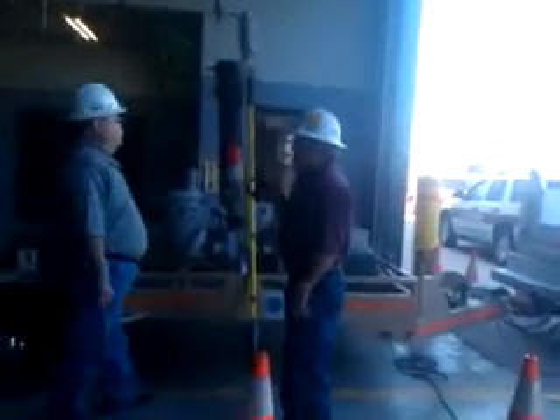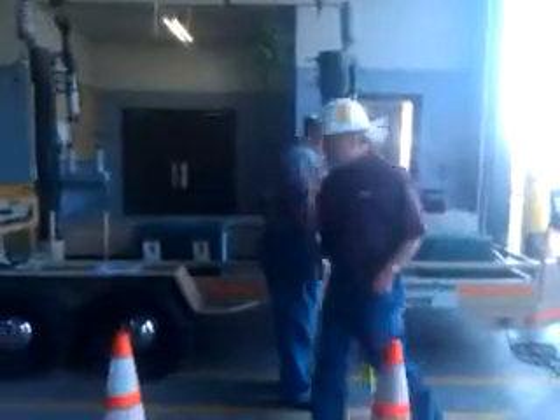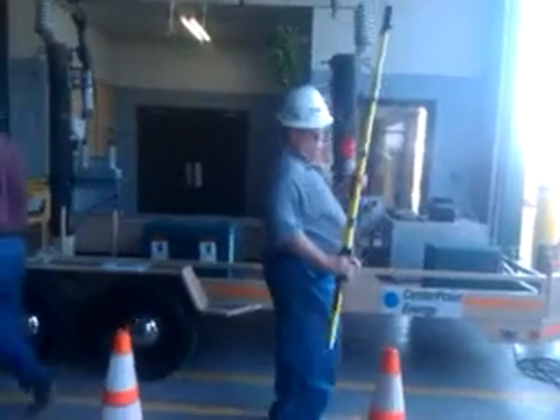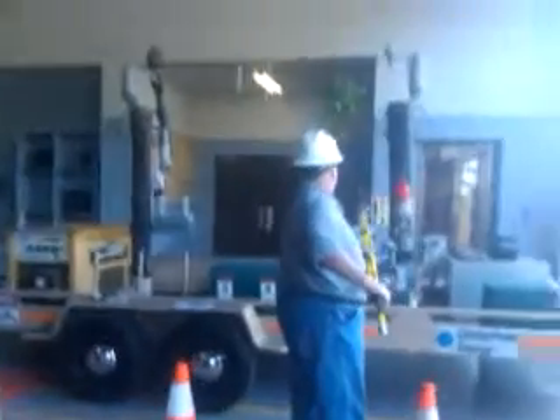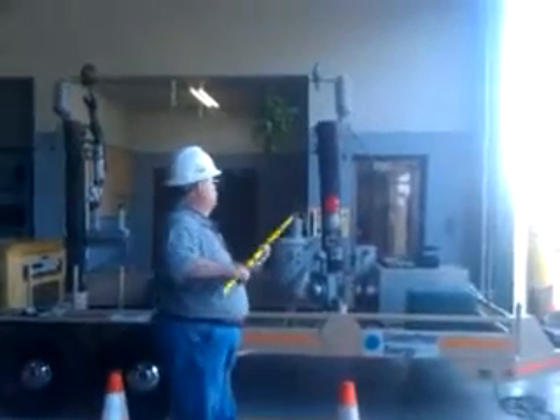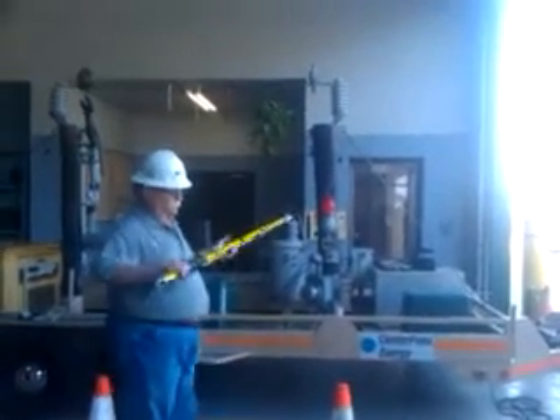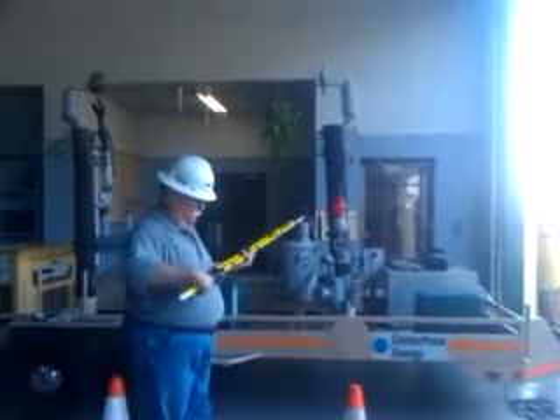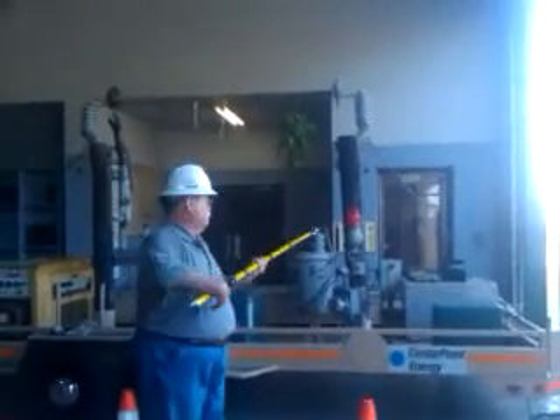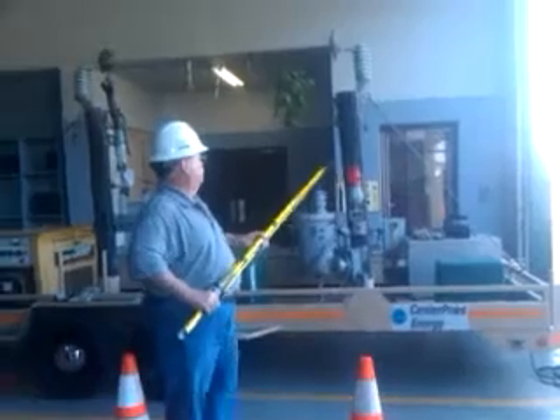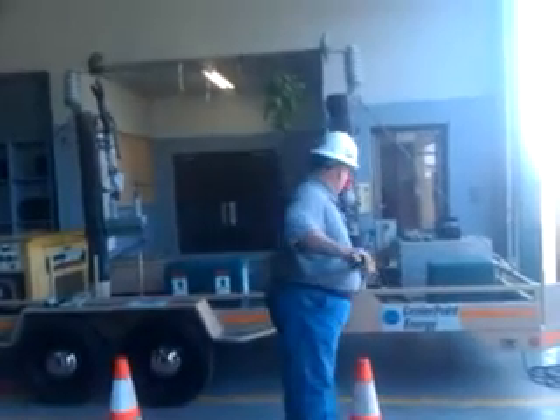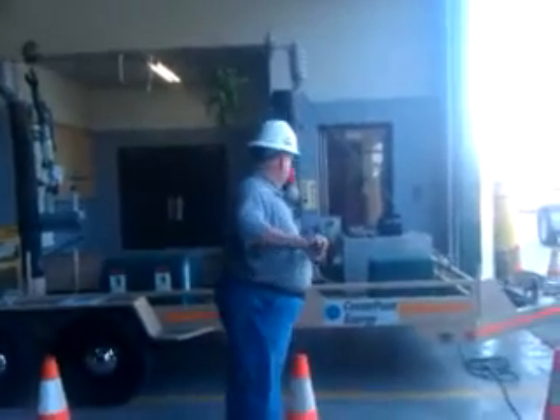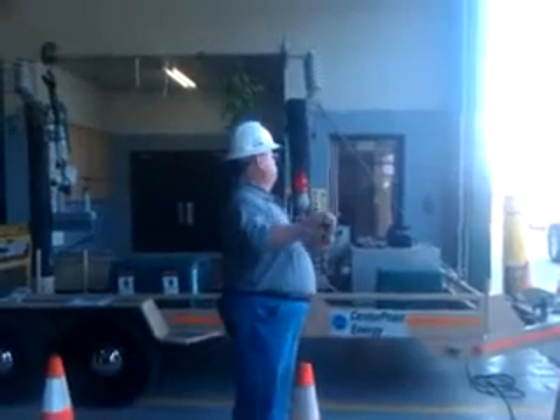Greg, are you ready to take the grounds off? Okay, Greg's going to take the grounds off our arcing trailer. And like we always say, if it's not grounded, it's not dead. We've got the truck and the trailer bonded together. We've got an earth ground over here for our safety, and we're also standing on 40,000 volt rubber mats. We've got our cones on it. We've got a 100,000 volt hot stick. Okay?